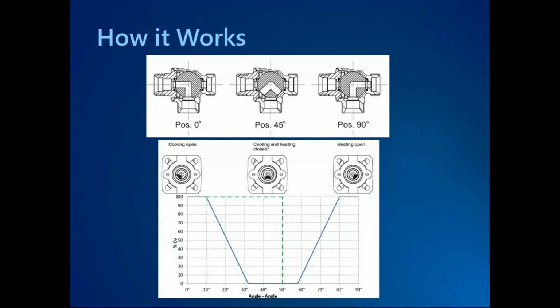And we can look at how it works in a little bit more detail here. So a 6-way control valve is just 2 3-way control valves stacked on top of each other. Both of them are L-ported, and both of them operate with one another at the same time. So as you can see, starting from position 0 degrees, you would have your cold water flowing in from the left-hand side, going through the top of the 2 balls, flowing to your zone. It comes back and flows through the bottom of the 2 ball valves and back out to the cold water return. As the 6-way begins to rotate from 0 degrees towards 45 degrees, we actually are able to get modulating control on these 6-ways. There's typically only about 20 to 30 degrees of rangeability, depending on the manufacturer, when it comes to modulating control.